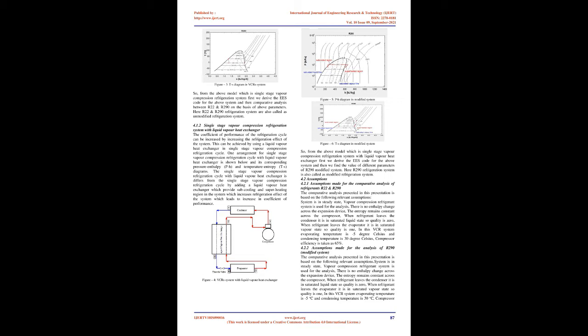The lower liquid density of R290 reflects the lower requirement of refrigerant mass, resulting in lower friction and better heat transfer coefficients in the evaporator and condenser. Refrigerant viscosity is a major source of irreversibility and influences condensation and boiling heat transfer coefficients. R290 has lower viscosity and higher thermal conductivity, which improves the performance of the condenser and evaporator. The higher specific heat of R290 gives lower discharge temperature.